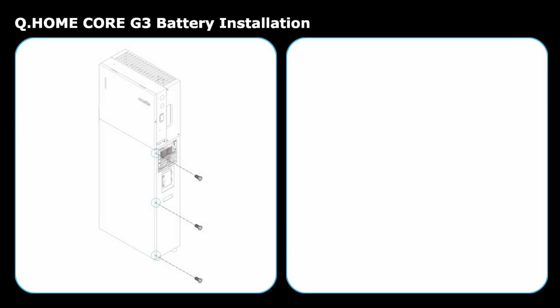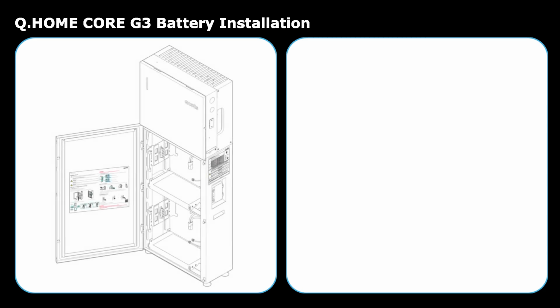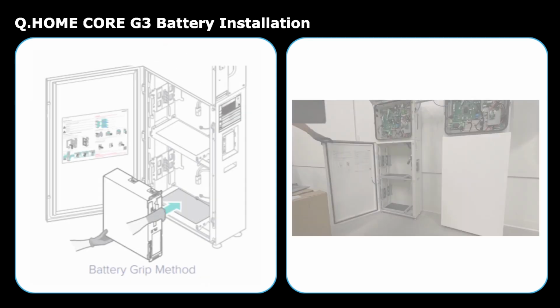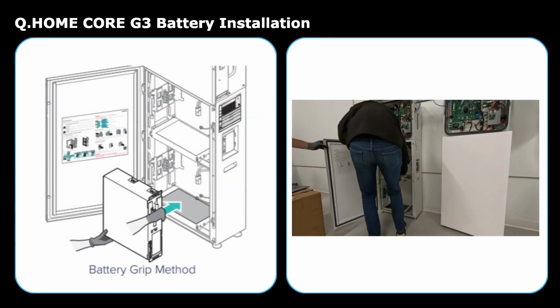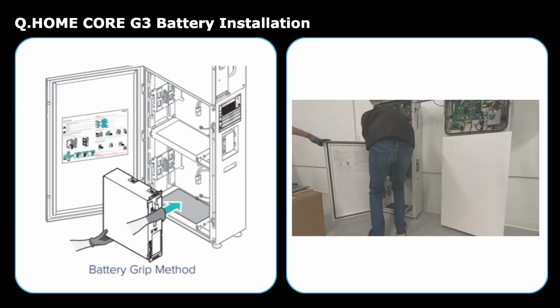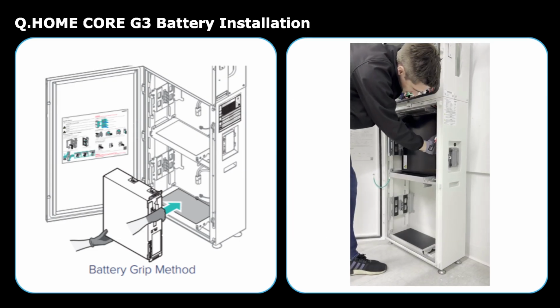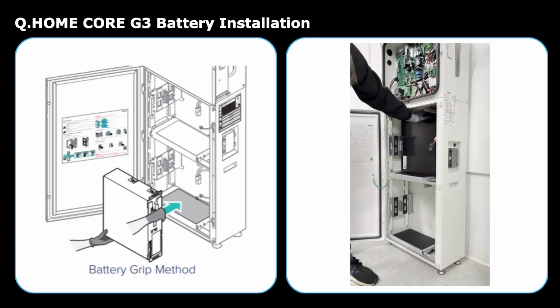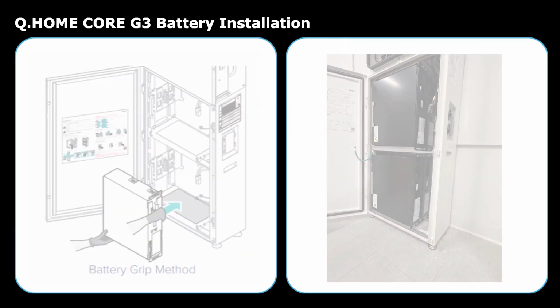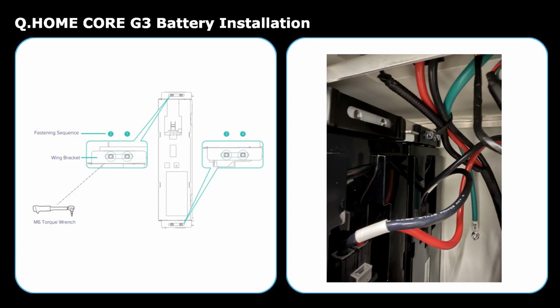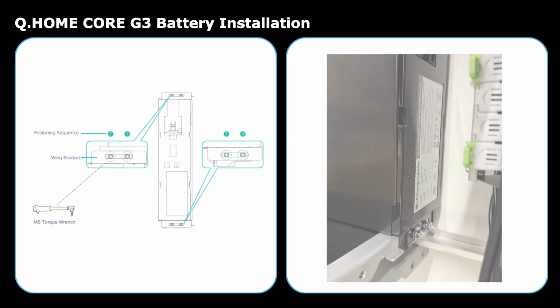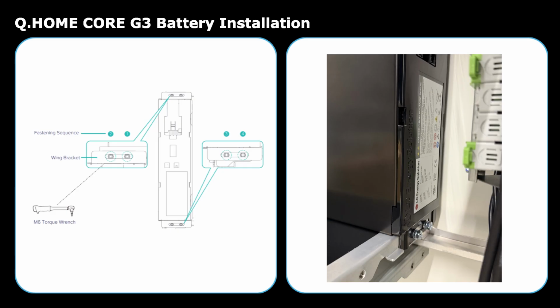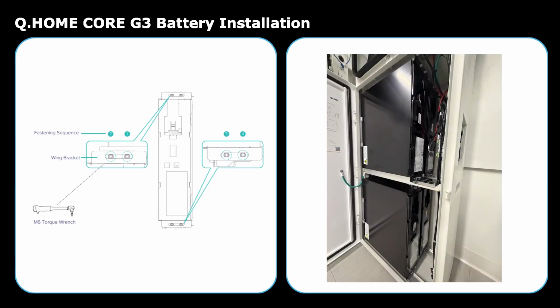To open the front panel of the Q.HOME CORE G3, remove the 3 bolts on the side of the battery door. Then, insert the battery modules one at a time. Secure each module using M6 by 12 mm bolts. Tighten the bolts in a counterclockwise order, starting from the top bracket.